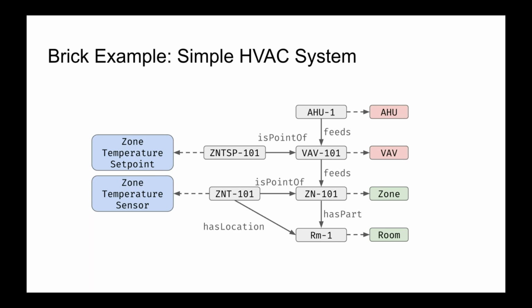My air handler unit to my VAV to my zone is sort of the flow of air. That zone consists of a room, and my temperature and set points are related to the entities VAV and zone respectively. I also have the 'has location' relationship that indicates the zone temperature sensor is actually located within that room.